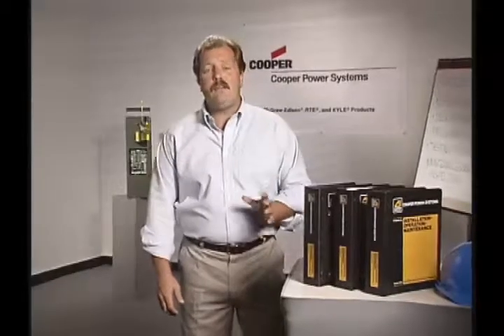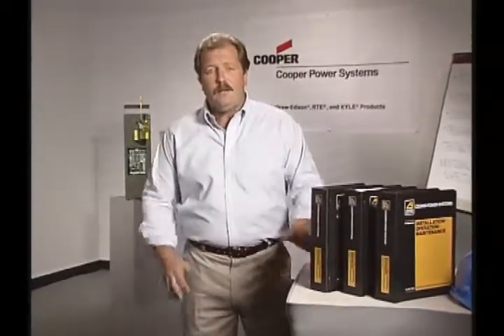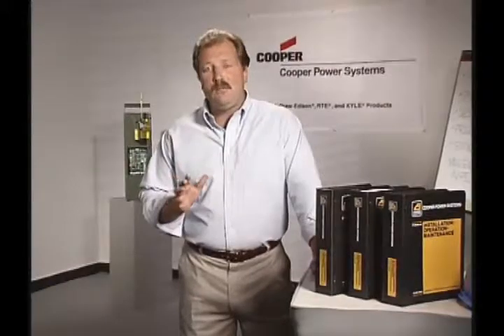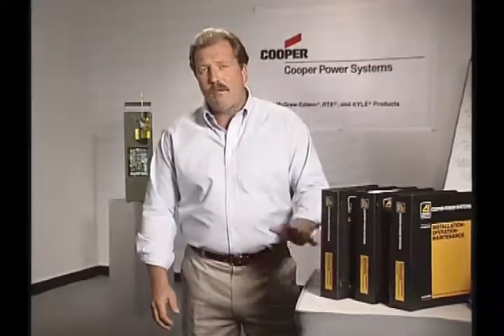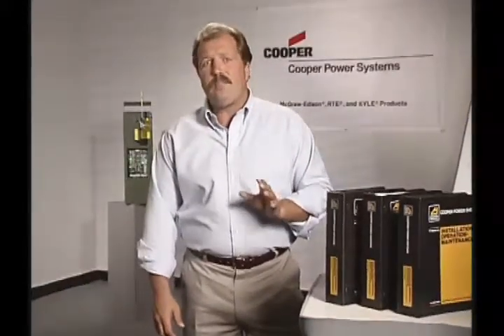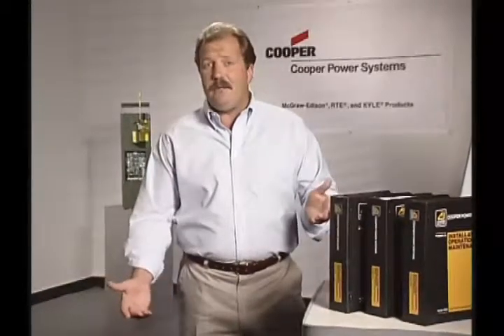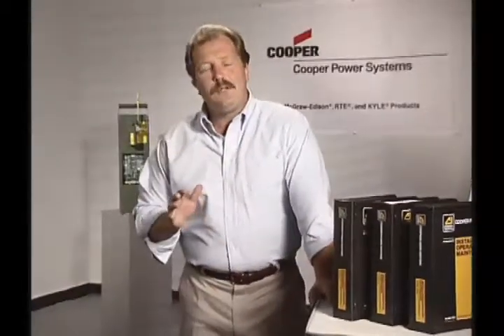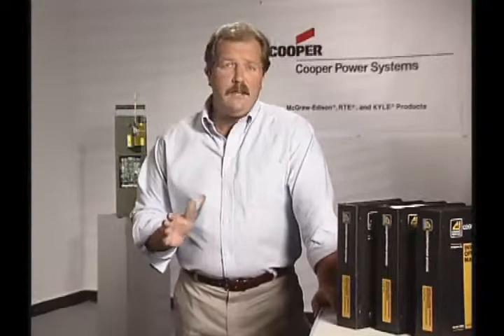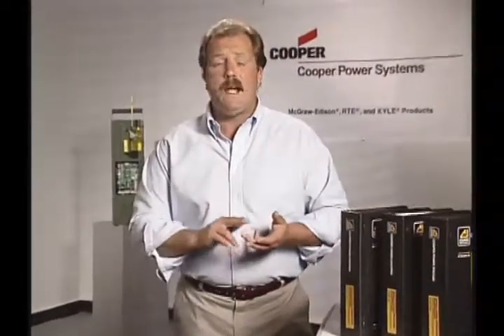The Kyle Type VFI vacuum fault interrupter represents the latest technology in pad-mounted switchgear. Overcurrent protection is accomplished with Kyle vacuum interrupters instead of fuses. The self-powered electronic control provides an extensive choice of minimum trip settings, time current curves, and operating features. The VFI's resettable breaker mechanism allows immediate service restoration, eliminating the added downtime and expense associated with changing out conventional fuses.